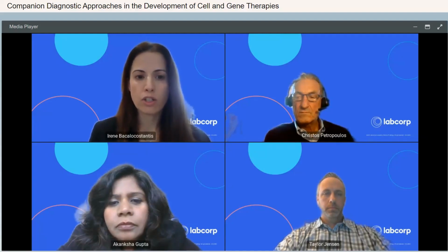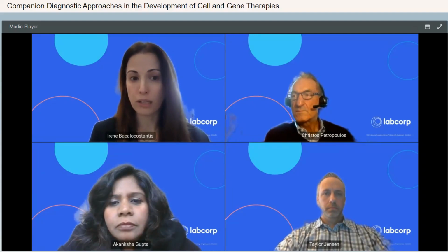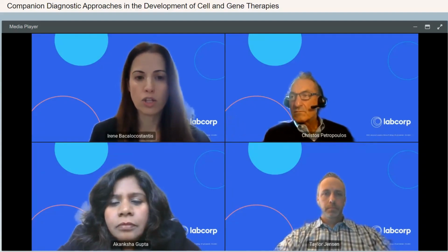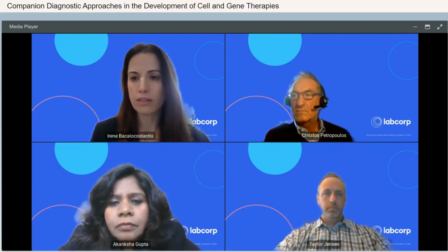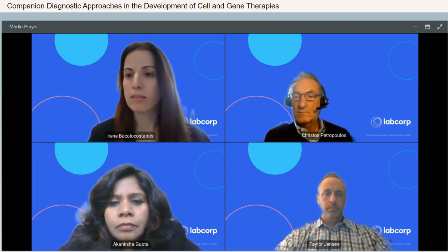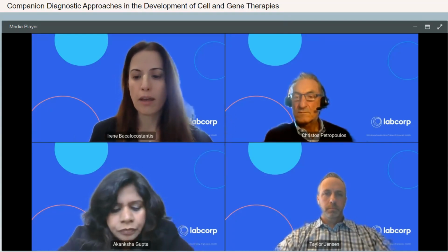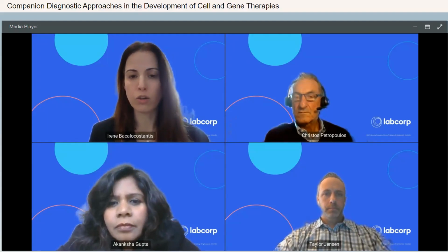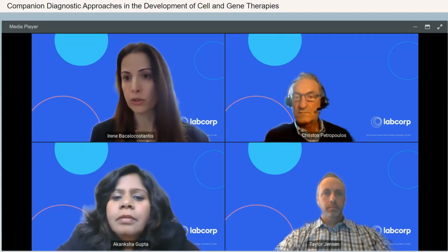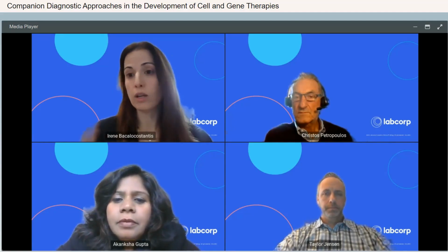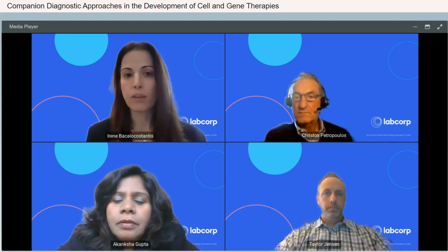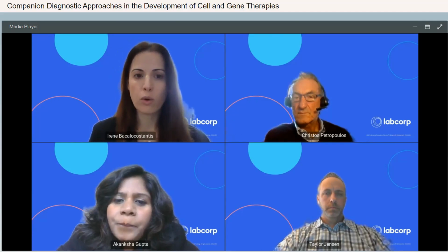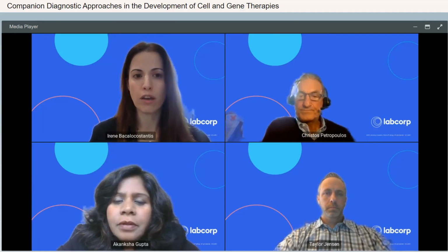Also to take under consideration early on in your development is your commercialization plan. So as Taylor, as you suggested, global distribution of an assay or a single site, it makes a difference in the requirements as far as maybe some of the studies that would be required, and also how you will be testing these samples later on. Do you need a globally distributed kit, or will samples from the rest of the world be coming to a single site in the US or anywhere outside of that particular country? And that makes a big difference because globally, regulatory requirements are very much linked to the specific country and that model.